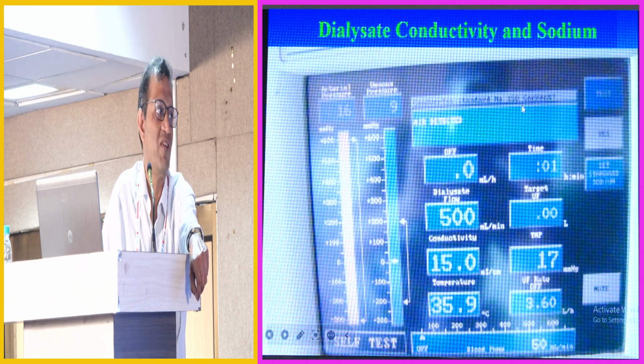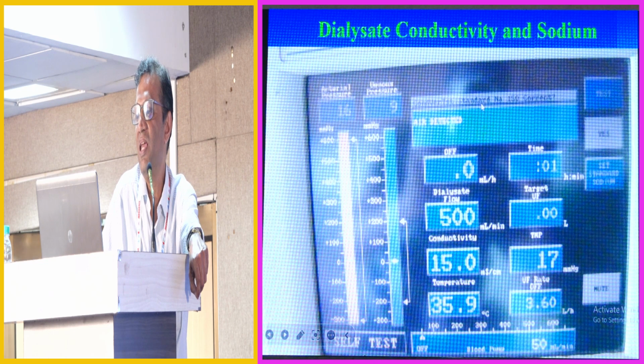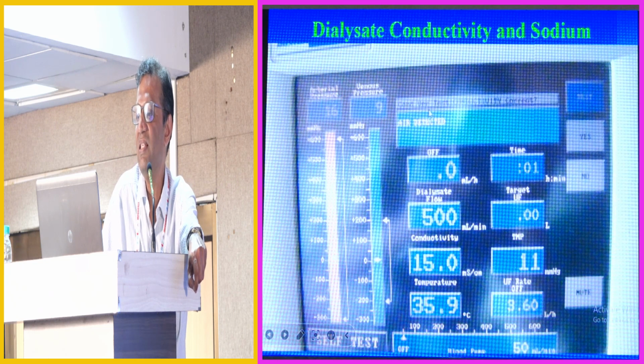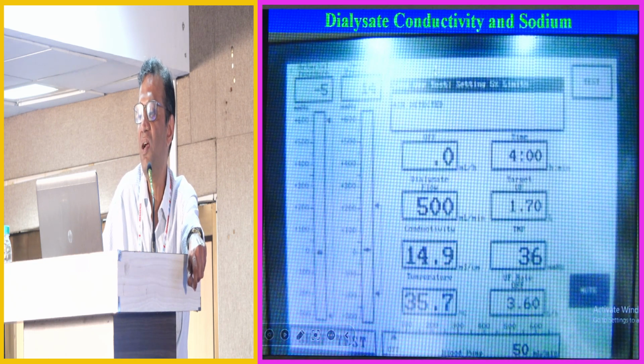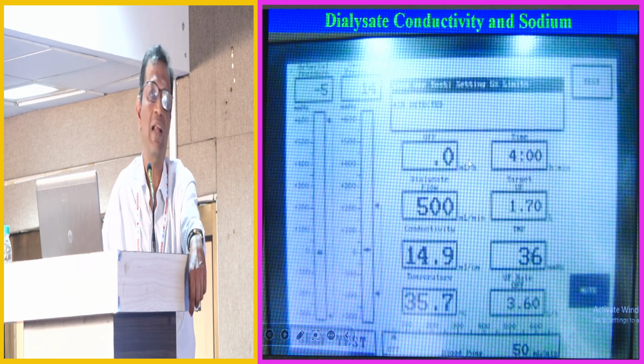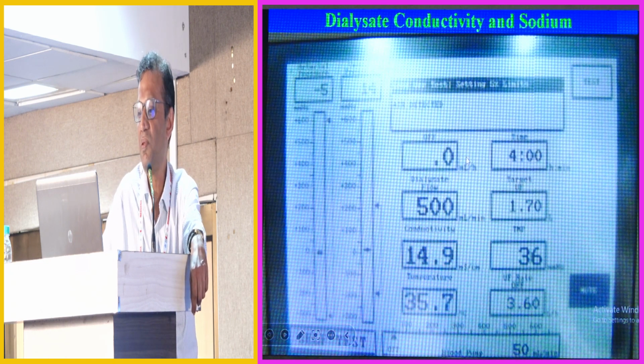and I would change that value to 150. So then the machine asks me, is the standard sodium of 150 correct? It corresponds to the conductivity. So now I say yes. The machine then says conductivity correct? Again I say yes, and then the machine will set the conductivity limits around the value which it has accepted.